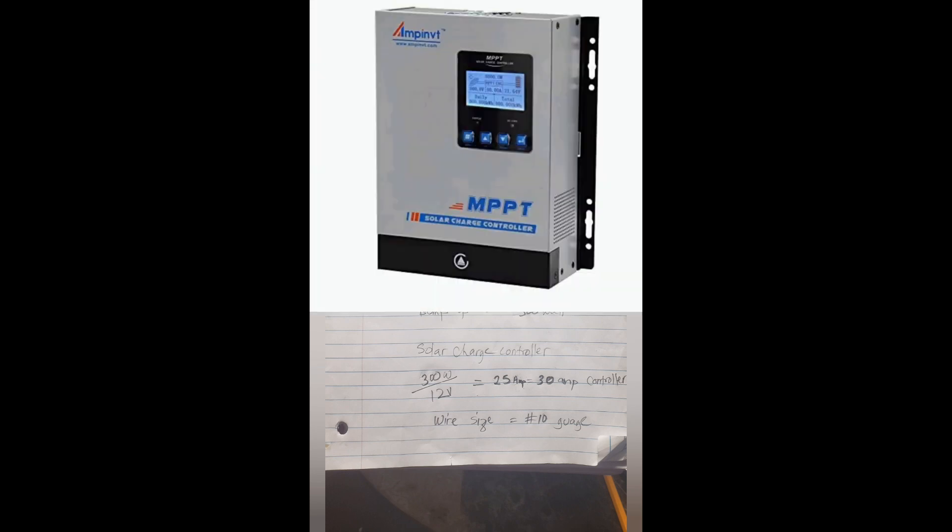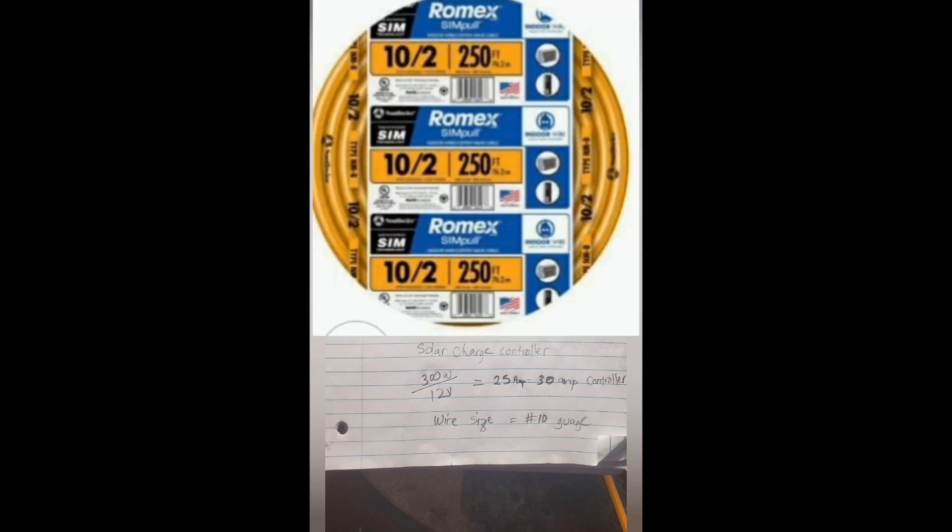Once you have your solar array, you need your charge controller. With 300 watts, divide by 12 volts — that gives you 25 amps. You want to bump that up to at least 30 amps, because you're not going to find a 25-amp controller anyway. Bumping up to 30 amps gives you the correct wire size for wiring your system. You always want to bump things up a bit so you have a buffer in your system and everything stays safe.